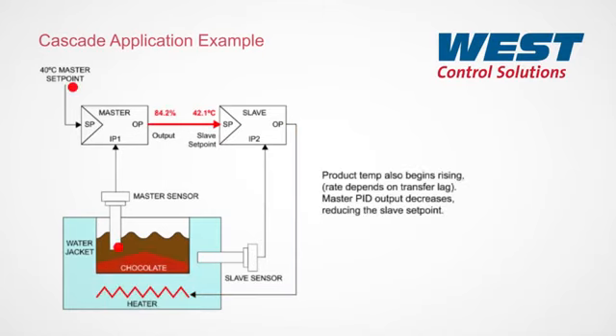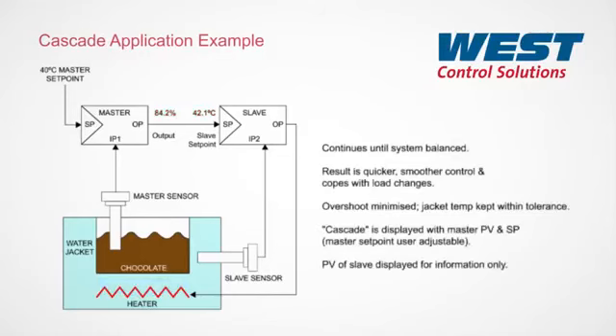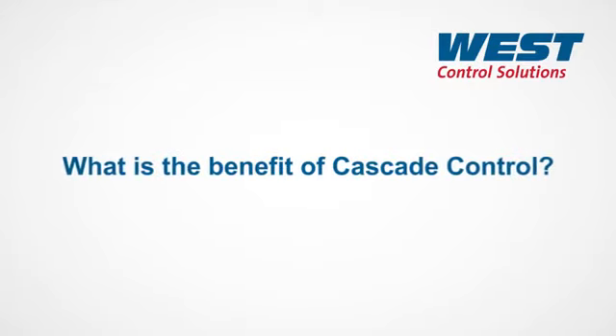This lag makes temperature overshoot or unstable control more likely. As a result, cascade control can be used to improve control performance. The master controller measures the chocolate temperature and feeds the set point to the slave, which monitors and heats the water as required. If the temperature of the chocolate is rising too fast, the set point is reduced to the slave and the controller can then vary the heat applied accordingly. Temperature control performance is improved due to faster responsiveness, resulting in minimized overshoot and less fluctuation in control.